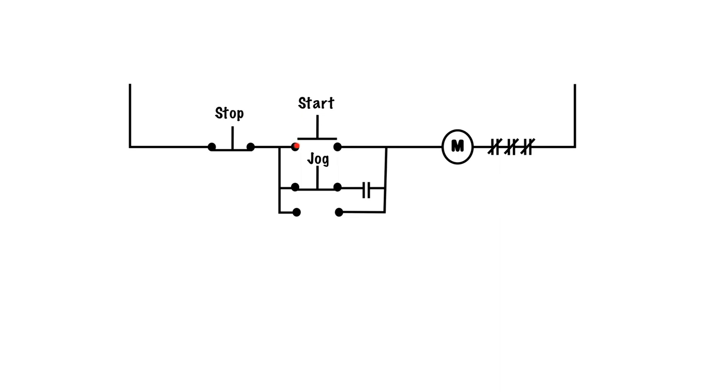So we have our typical stop normally closed push button, we have our start normally open push button, we have our coil, we have our overloads, we have a holding contact that is associated with this M coil. And then we have this two position push button where right now it's in the normally closed position, but if we press down on it it'll make contact with the normally open contacts on that side.